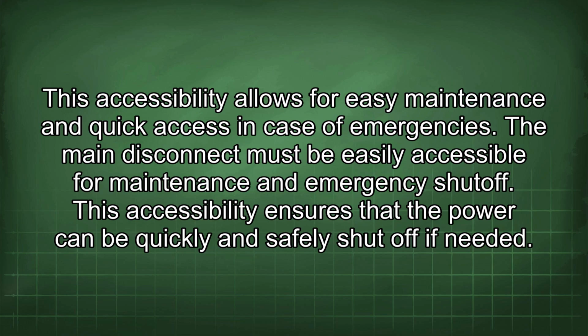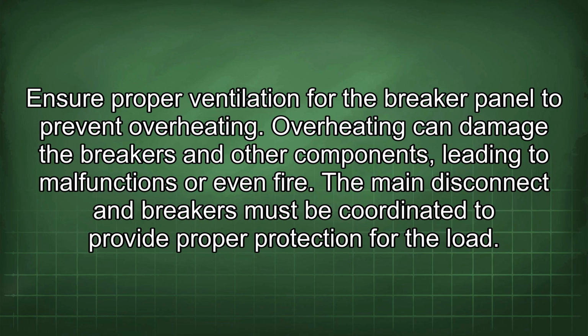The main disconnect must be easily accessible for maintenance and emergency shutoff. This accessibility ensures that the power can be quickly and safely shut off if needed. Ensure proper ventilation for the breaker panel to prevent overheating. Overheating can damage the breakers and other components, leading to malfunctions or even fire.